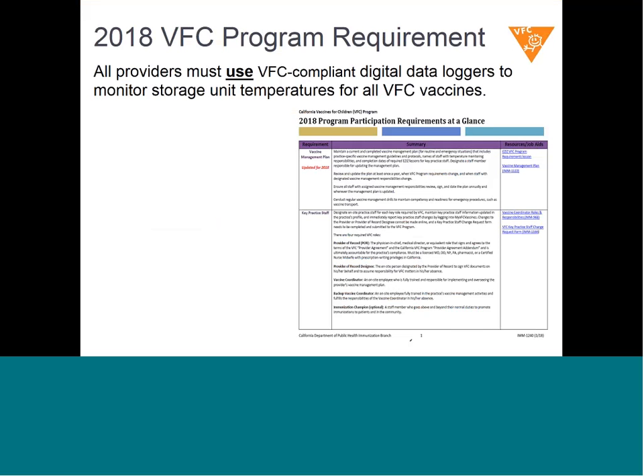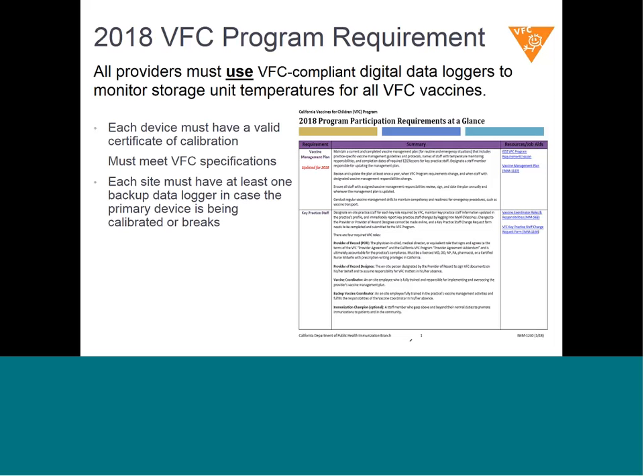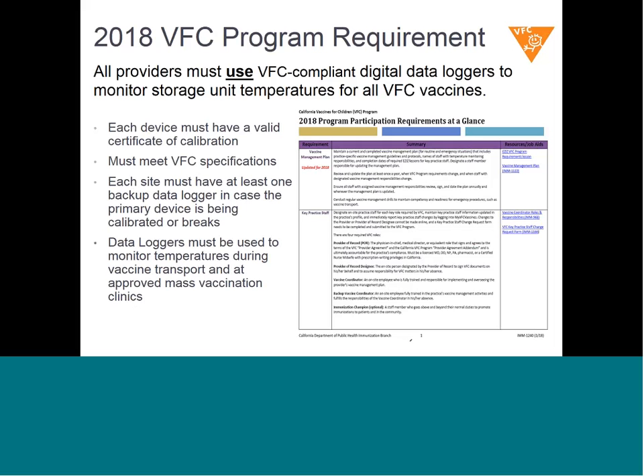So in case you're not aware, in the 2018 Program Participation at a Glance document, you'll find additional information on this requirement. In this document, you'll find where it states each device must have a valid certificate of calibration. It must also meet VFC specifications. And each site must have at least one backup data logger in case the primary device is being calibrated or breaks. And you must use a digital data logger to monitor temperatures during vaccine transport and at approved mass vaccination clinics.